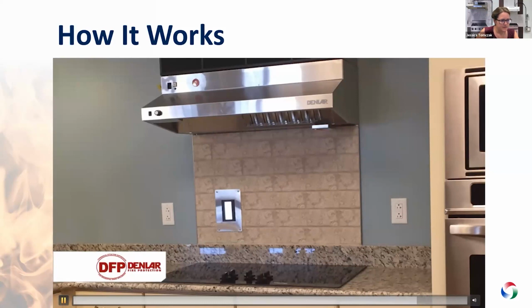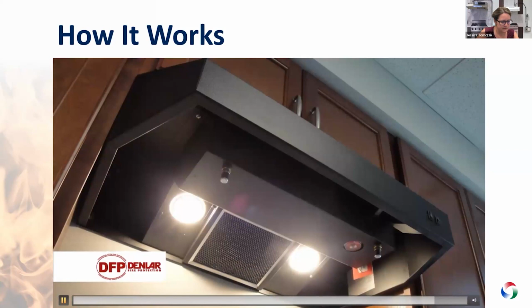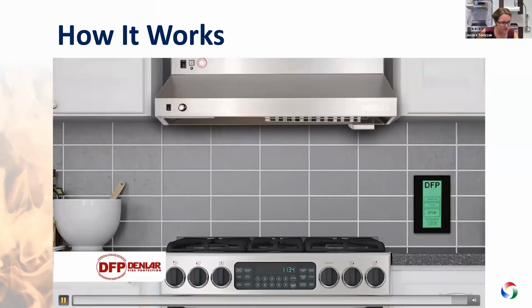And this is just a couple installation pictures so you can see what it looks like. I see there's a question about the flare. So if there was a flash fire, for example, we offer a manual pull station that the person on site could utilize in order to discharge the fire, and that's going to be the path of egress, so it shouldn't be anywhere in close proximity to the stove. Hopefully that answers your question.